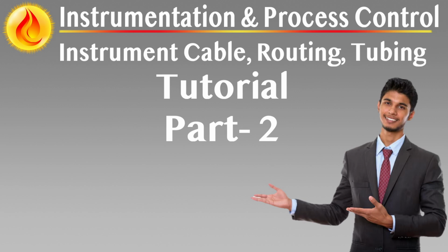Cables carrying intrinsically safe (IS) signals must be segregated from non-IS circuits per IEC 60079-14 requirements. Signal level class 5 cables, e.g. solenoids or power circuits, require physical separation from lower level signal classes 1 to 4 due to their higher energy content and greater electromagnetic emission potential. However, pneumatic tubing and fiber optic cables, signal class 6, may be bundled with any electric cable types due to their non-conductive or non-interfering nature.